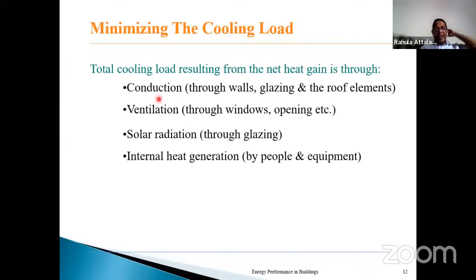So the first element is the conduction, that is heat interaction between the outside and inside through walls, glazing and the roof. The second is again through windows and openings, the ventilation. The air will move from inside to outside or outside to inside, an air exchange. That's called ventilation. It may be voluntary or involuntary. Sometimes it's involuntary, and that's called infiltration. We expect everything to be closed, airtight, but that's not so.